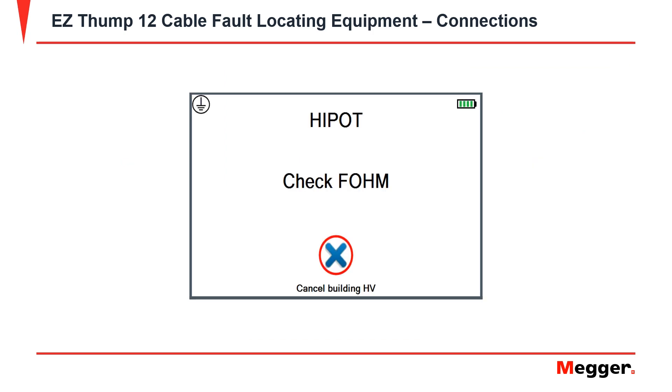Before you start a test, you may see an error message that reads 'Check FOHM.' Check FOHM means that your high voltage return lead and your grounding cable are too far apart.